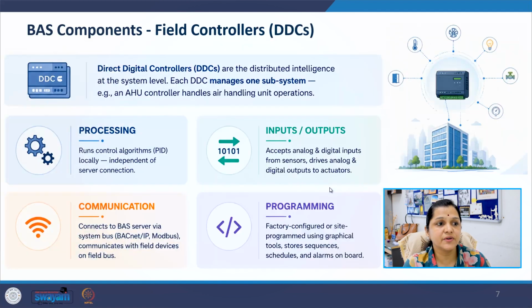Then comes building component field controller, that is direct digital controllers or DDC. They provide distributed intelligence within building automation system. Each controller manages a specific subsystem. For example, one controller may manage an air handling unit, while another controls chilled water circulation. So DDC runs control algorithms locally. Even if the building automation system or BAS server connection fails, the controller can continue operating independently.